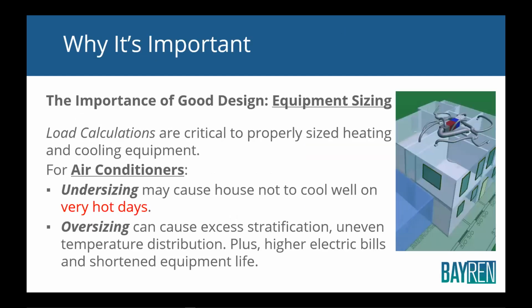So let's talk about equipment sizing, the importance of good design related to equipment sizing. You have to do a load calc to properly size heating and cooling equipment. You've probably heard the old 500 square feet per ton, and some of the more progressive installers say, oh, we do 600 square feet per ton. Well, that's not a load calc. Square footage of the house has very, very little to do with the load of the house.